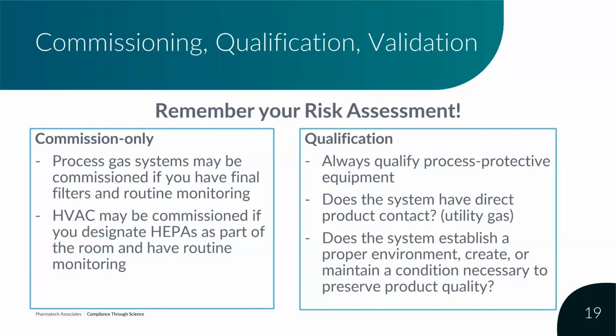So then we go from commissioning to qualification. We always qualify the equipment that protects the process — this is not negotiable. Does the system have direct product contact? Hey, wait, didn't I talk about utility gas systems on the commissioning-only side? That's your risk assessment. If you assess your risk of product contact — if we're bubbling oxygen and CO2 through a bioreactor, you may need to do something different compared to using the gas in a way that doesn't contact the product as much.